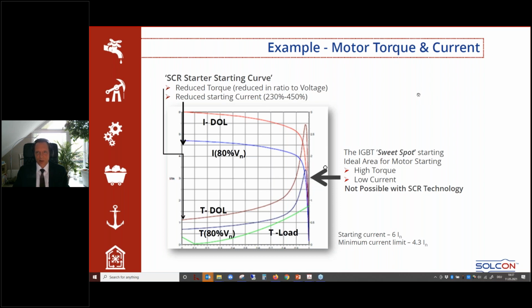One example, motor and torque and current and so on. What you see here is the current at full voltage, current at reduced voltage, and vice versa for the torque. Full torque, reduced torque. Here you have a portion of the torque speed curve where you have to pay attention. Starting current here is six times I nominal. In this case, we limit it to 4.3 I nominal.